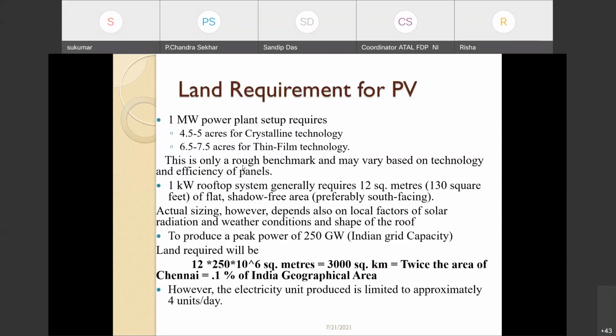So from this, we see that if we have to go for a 1 kilowatt rooftop solar system, then we have to go for only 12 square meters of area, which converts to 130 square feet of rooftop area. And that should be shadow free area, in fact. And if we extrapolate that to the whole Indian system and Indian grid, which is 250 gigawatt, then we get approximately 3000 square kilometers, which is just 0.1% of the whole India geographical area.